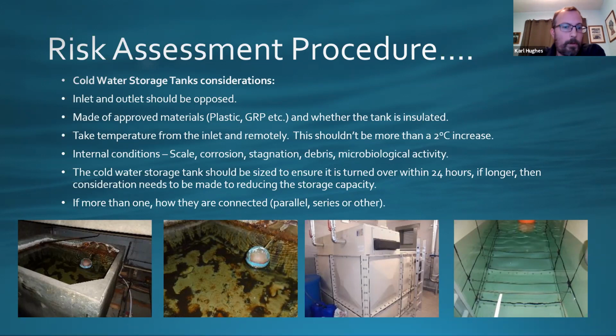You've obviously got systems that are on mains water, so we don't need to be in there. Last thing, you would check to see how they're connected, whether they're connected in parallel or series. If they're in parallel, you need to make sure that the inlets to both of them are balanced properly, so you're not getting one tank taking the brunt of the water and the other one becoming stagnated. And if they're in series, one of the things to look out for, usually when you haven't got the break of water going into the tank, which is aerating the water from the incoming main, is that you might get stagnation within the center tanks where there's no movement of water, just as the water rises and lowers and things like that.